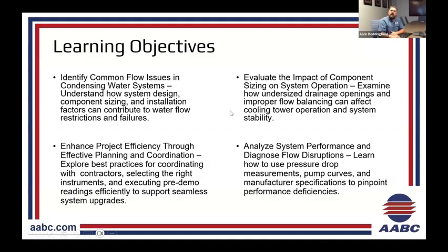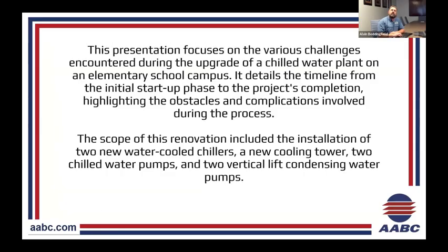Evaluating the impact of component sizing, system operations, and how undersized piping and drainage can cause improper flow balancing and cooling tower operations, and then analyzing performance and diagnosing flow disruptions, and learning how to utilize pressure drops, measurements, pump curves, and manufacturer submittals to pinpoint some of the performance deficiencies throughout the entire system. So for this presentation, I had 3 campuses where we experienced similar problems.